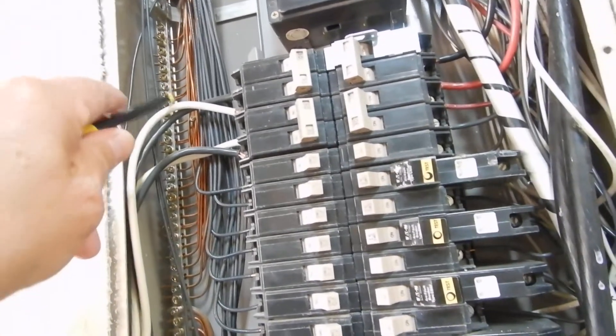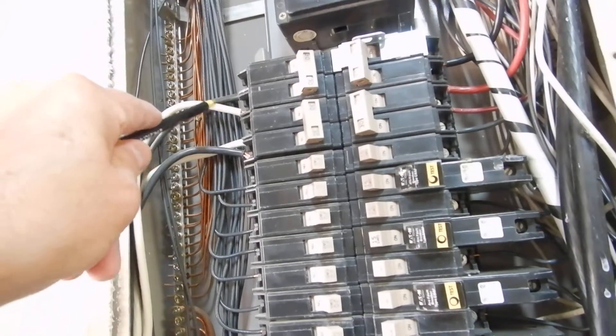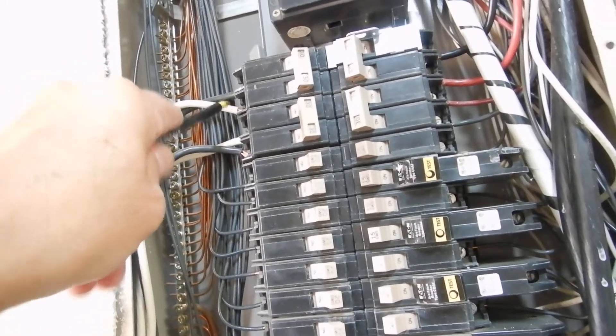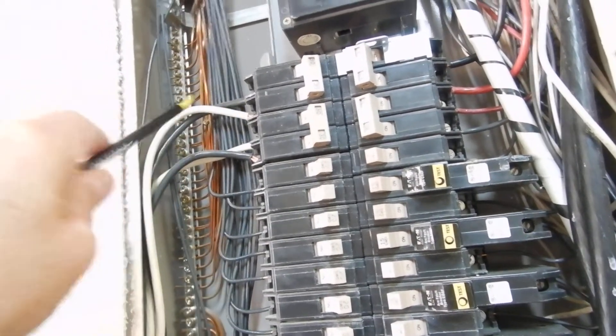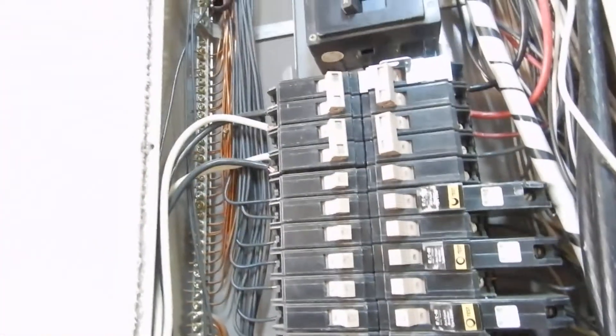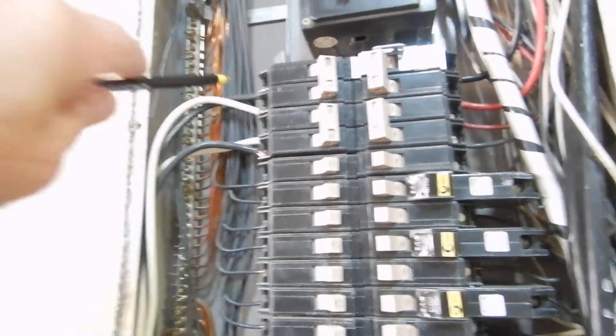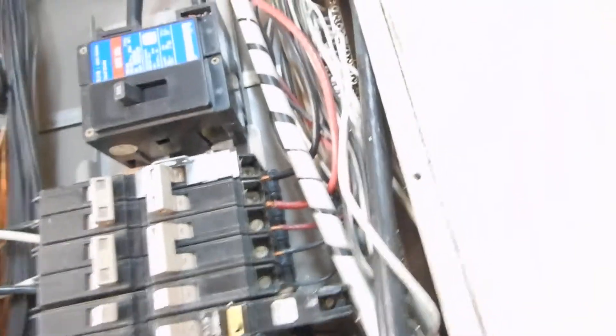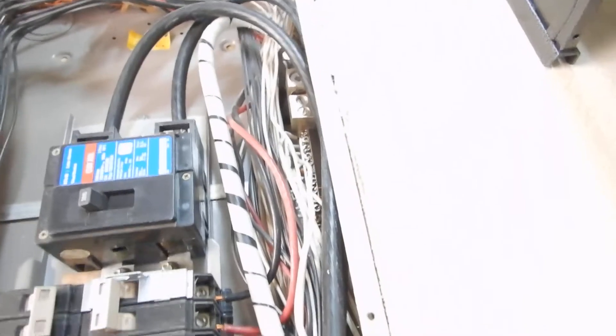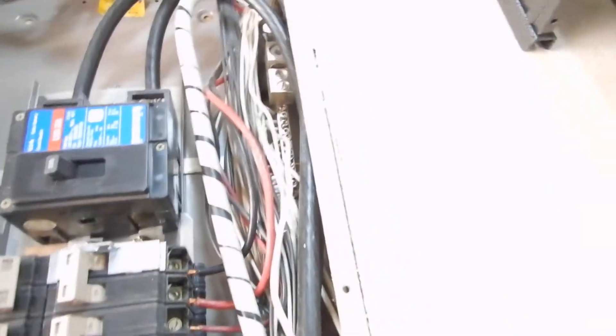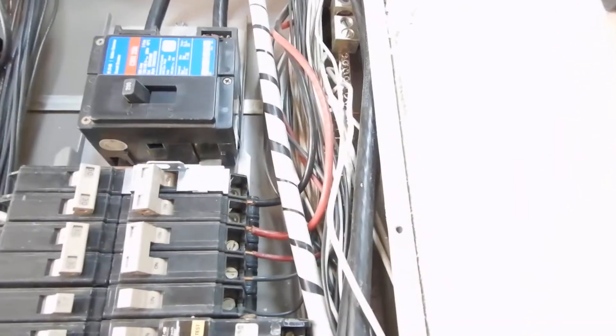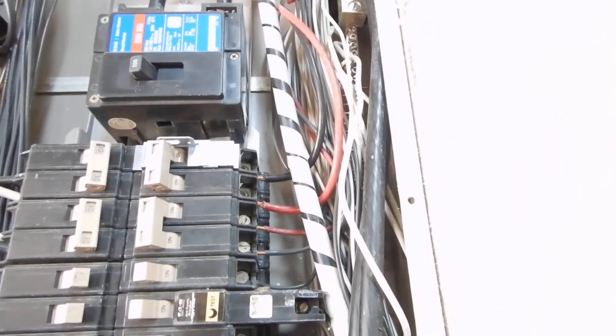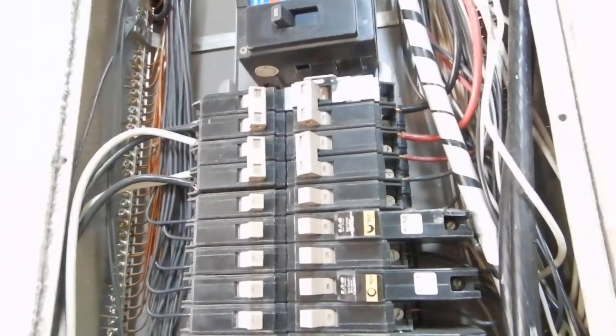Now, see the white cables come in here? Those are hot. If you don't know that's hot, you don't belong in this cabinet. I get that. But see your neutral right here? Your main neutral coming in? It's wrapped with white tape. Now, if you didn't know that was a neutral, again, you don't belong in this cabinet. But it was wrapped with white tape because the code said it was supposed to be.